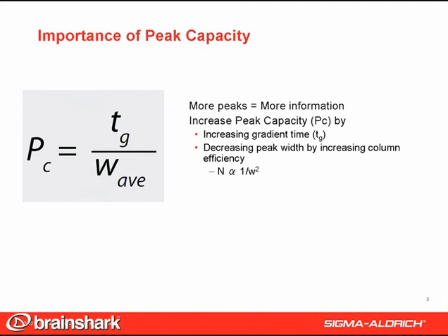You can increase gradient time, but this increases the analysis time, which is not desirable, or decrease the peak width. Since efficiency is inversely proportional to the peak width squared, a more efficient column will have lower average peak widths and will therefore exhibit higher peak capacity.